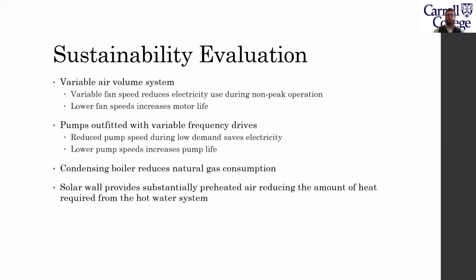Several options were used to improve the sustainability of this building. The variable air volume system is more efficient because the variable speed fan can reduce during non-peak operation. This saves on electricity costs, and also running the fan at lower speeds increases motor life. The pumps have also been fitted with variable frequency drives, so their speed can be reduced to save electricity. The lower pump speed increases pump life as well. The condensing boiler was also selected because it has reduced natural gas consumption. This decreases the carbon footprint of the building. The solar wall also provides a substantial amount of preheated air. This should allow the boiler to not have to run nearly as often as it would if the solar wall wasn't there.